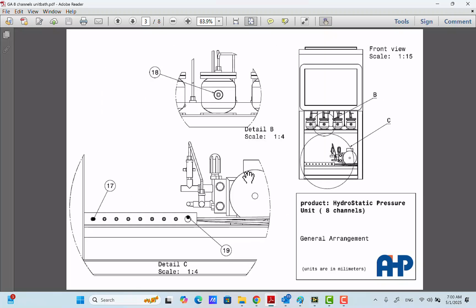Yeah, the other important point is the cap of the pump. There is a yellow cap on the pump itself. Normally, for transfer of the machine, the transfer cap of the pump is used. The transfer cap has no hole on it, but when you receive the machine and you need to fill the oil inside the pump, you need to change the cap. The cap that is used for operating the pump has a hole in the middle and also has two marks for the oil level inside the pump. Don't forget to check the oil level and to fill it in case of need.